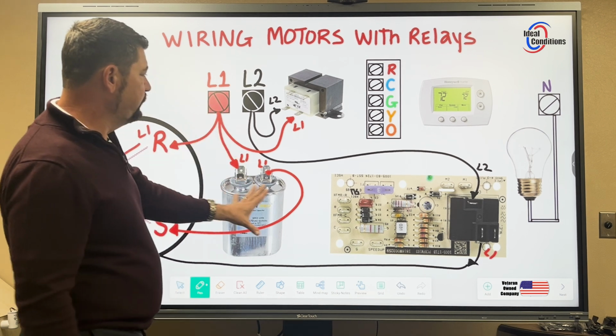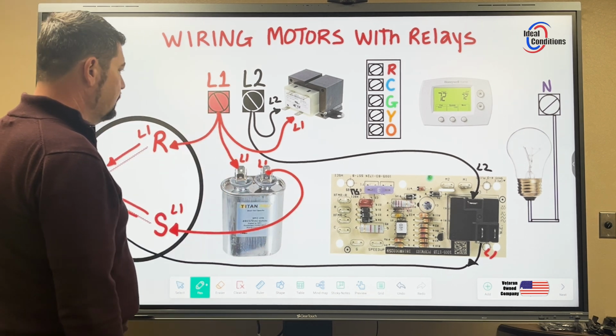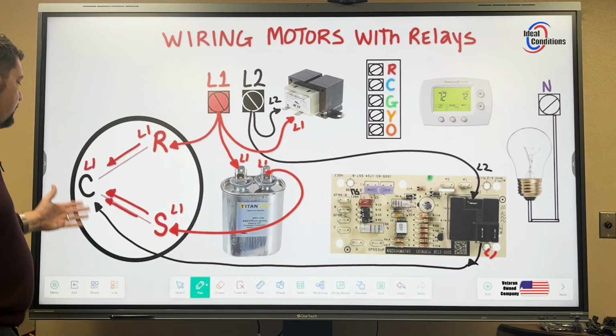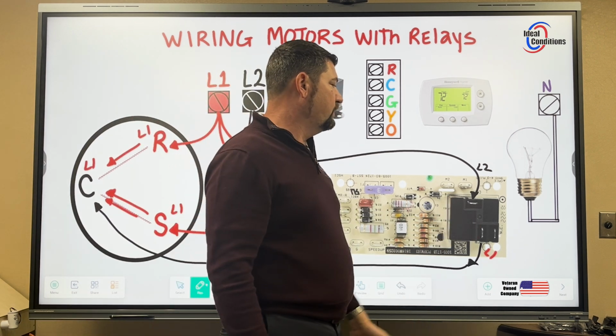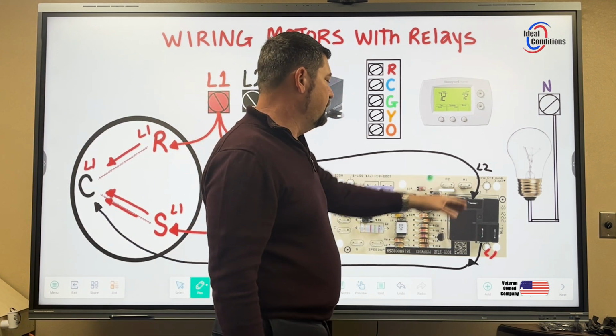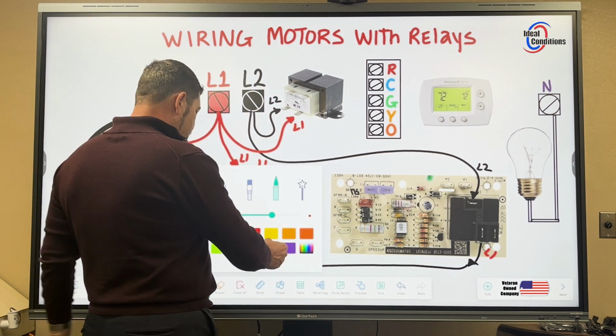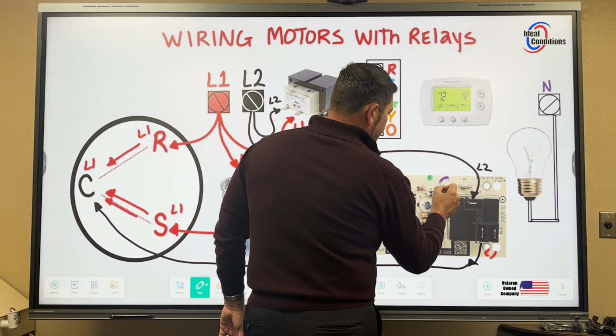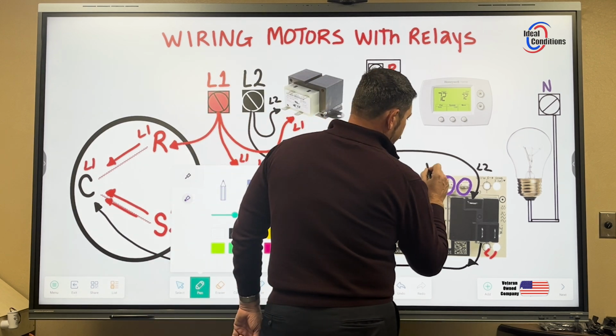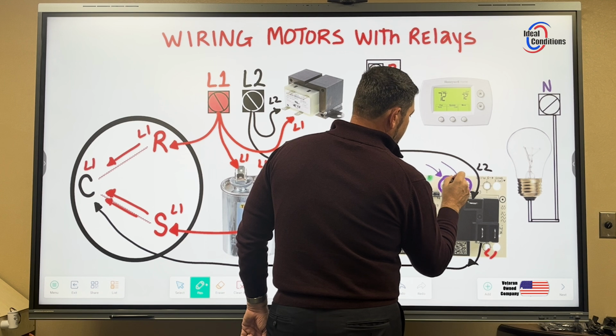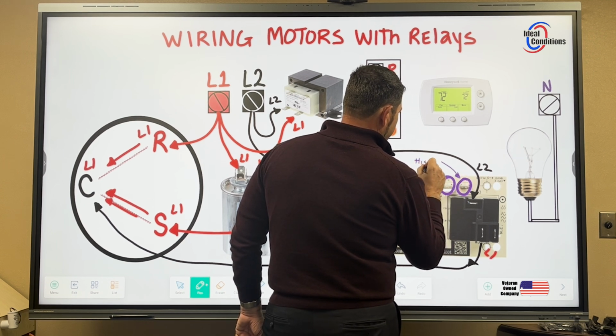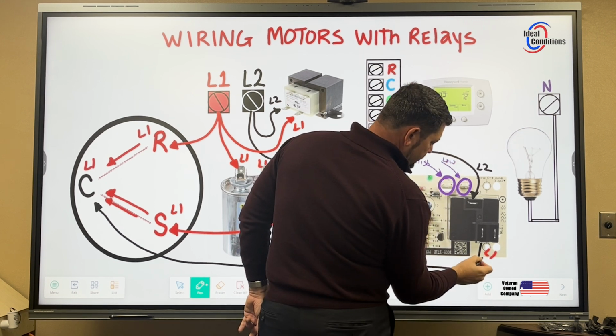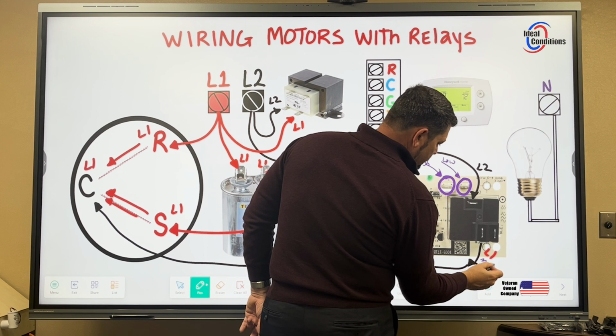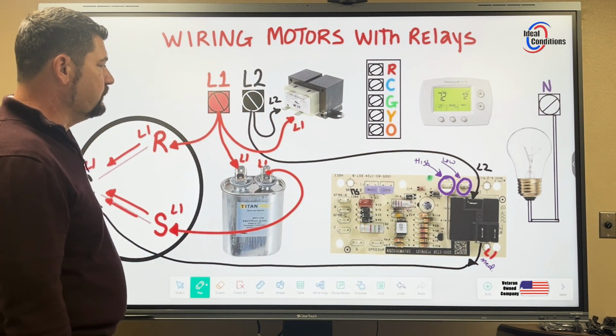Okay, where else does high voltage need to be wired to? That's it. Now, I don't have 3 speeds here, so I'm just going to assume this is medium speed or high speed or low speed, doesn't matter which one, but the other 2 would be parked on M2 and M1. So I'm going to go ahead and just pick a different color. We'll pick purple. I'm going to say here and here are going to be parked terminals. So I'm going to write that in. I'm going to say these are going to be inputs. And we're just going to say one of these is like high speed and one of these is low speed. And I'm just going to write down here that this is medium speed. Okay, those other 2 speeds that we're not using are going to be parked.